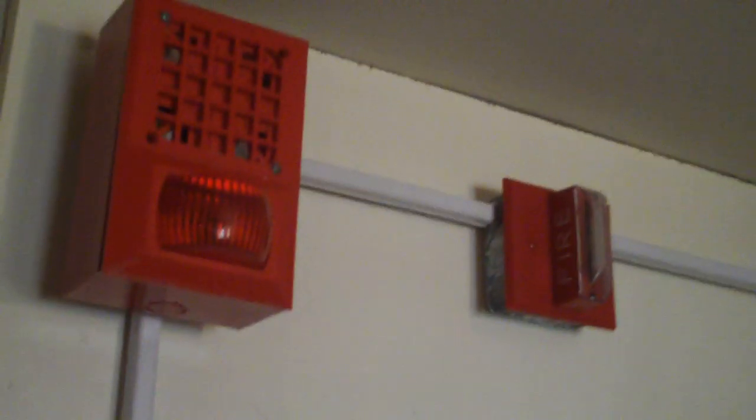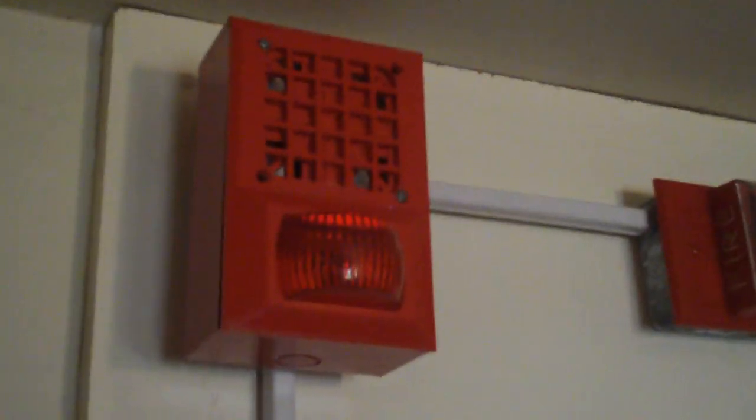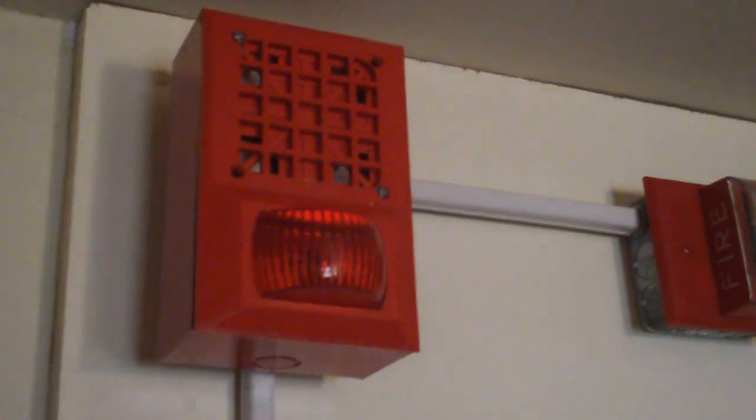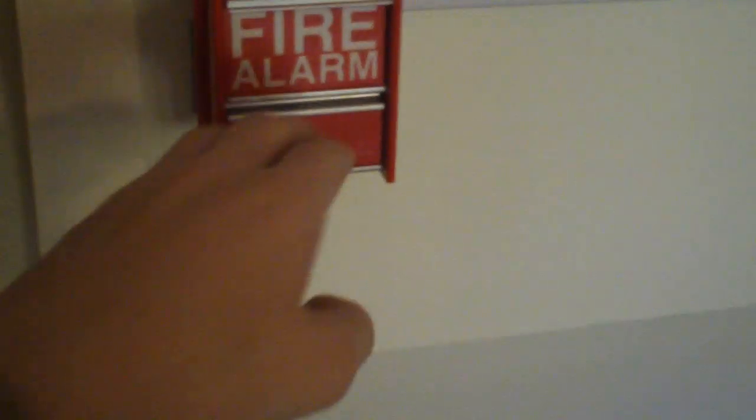So I have the MS2 pull station, a Wheelock 34T horn behind a space-age light plate, and a Gentex remote strobe. The system is going to be set on code 3, and the light plate is on pulse. So let's pull it.